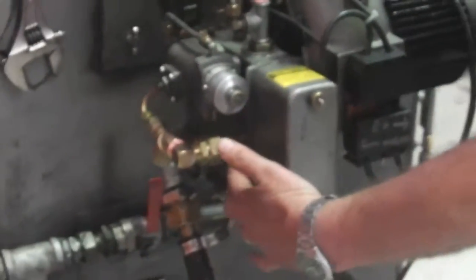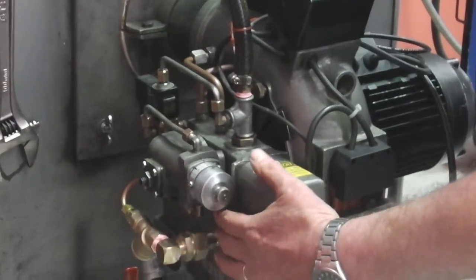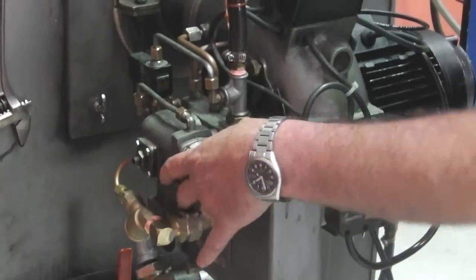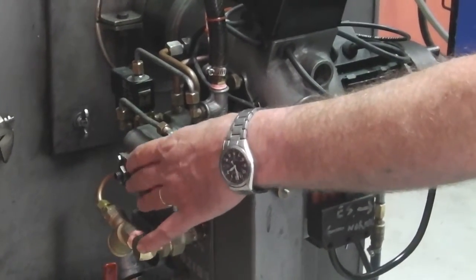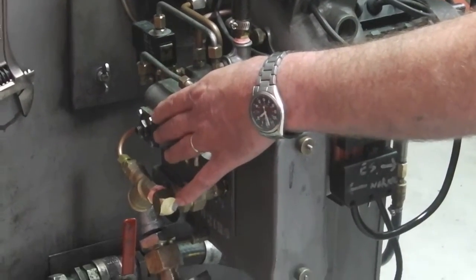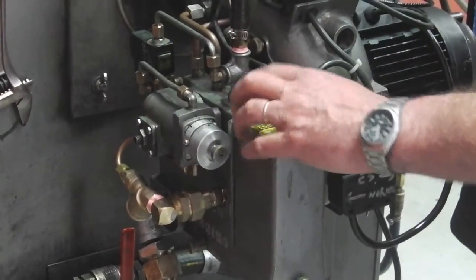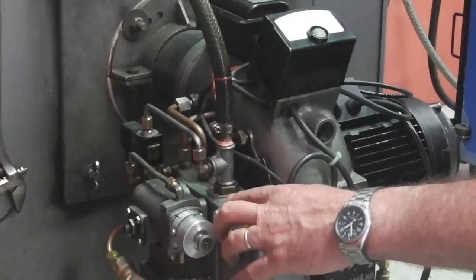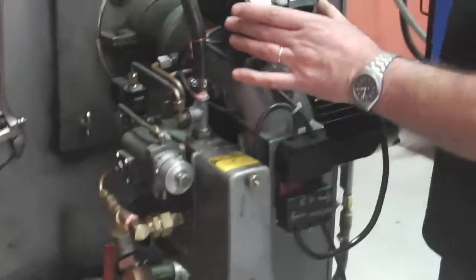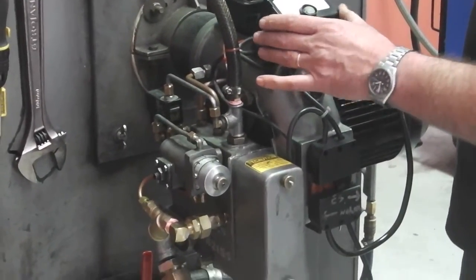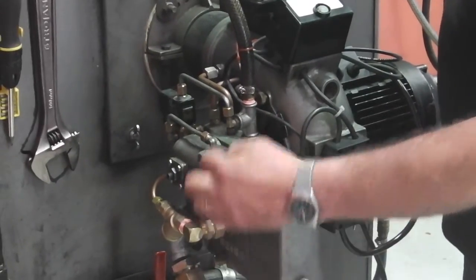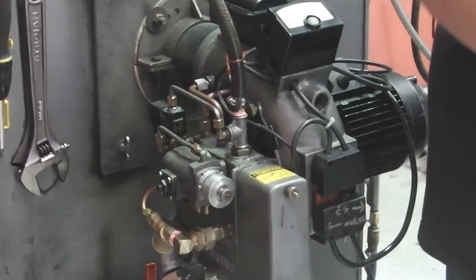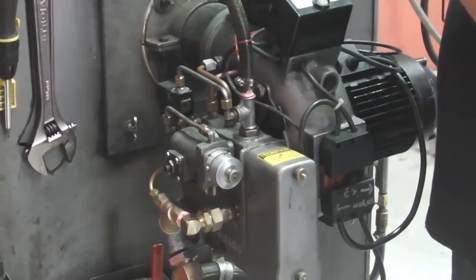Another thing that Pete just mentioned to me, everyone, is that depending what model you've got or what controller you've got, this pre-heat tank, if you put your hand on the top of there, that should be on standard waste oil, quite warm to touch. So it should be up at about 45 to 50 degrees. Some of the newer burner guns, plumbers and installers, will have an automatic delay until the gun starts up. That delay is pretty much based on this pre-heat tank getting up to around about 80 degrees centigrade, and then the gun is permitted to start.